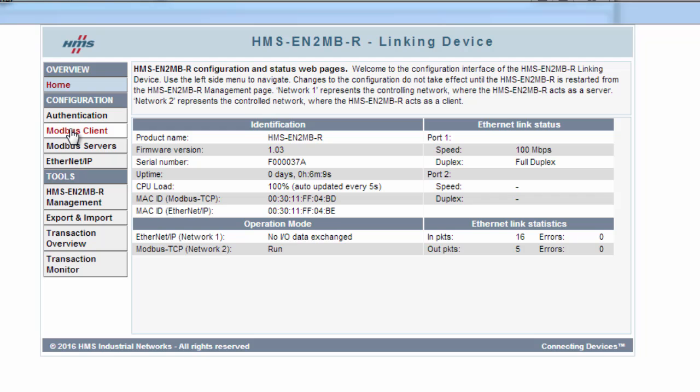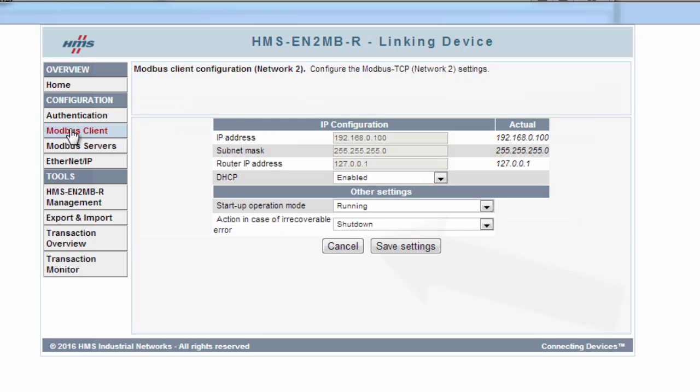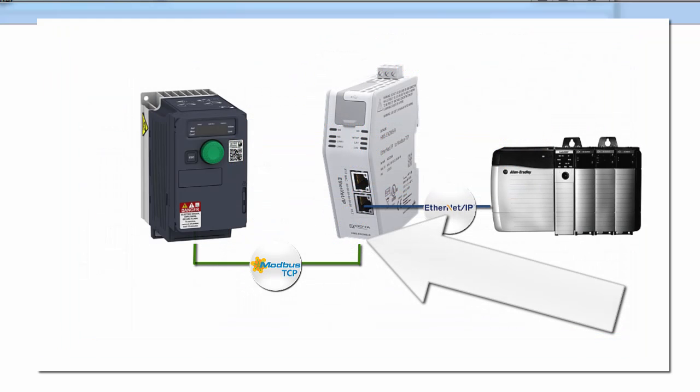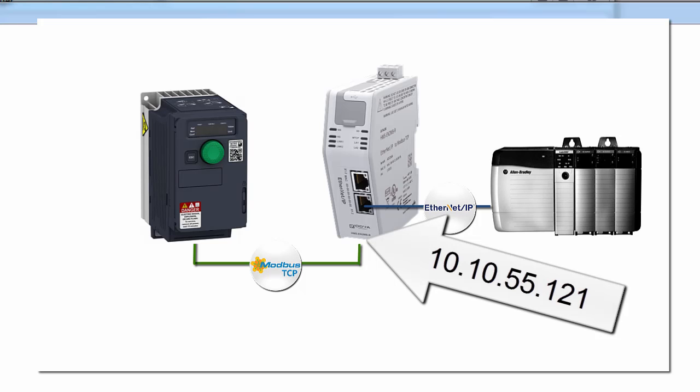I start with setting up the Modbus client. This is the bottom interface of the linking device. Here I want to use the IP address 10.10.55.121. Now this IP address does not have to be in the same range as the PLC, 10.10.55 in this case, but to make things easy in this demo I've kept them in the same range.